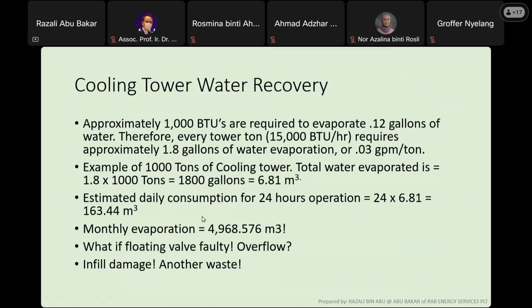If the unit is running 24 hours, it's approximately 163.44 meter cube. So monthly evaporation is about 4,968 meter cube. Earlier I showed a shopping complex with 4 chillers, but running only 1 chiller, about 1,200 tons, and their water bill is about 11,000 meter cube. You can see that water used for the cooling tower itself is already almost half of their actual consumption.